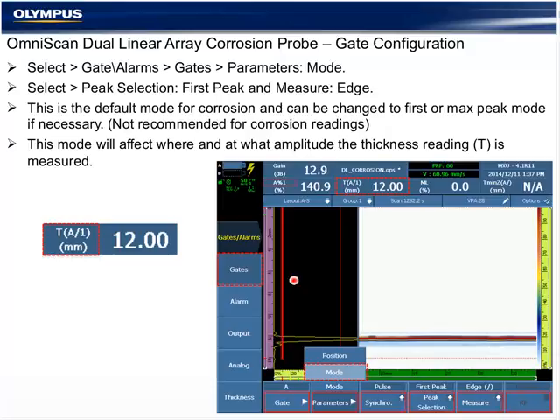The T reading is directly relevant to this inspection and is what we are looking at for the end result of our signal in the gate. And again, we'll also get an indication in the reading. In this case, we can see that the T or thickness reading is a function of gate A on the first peak edge mode, which is the recommended setting.